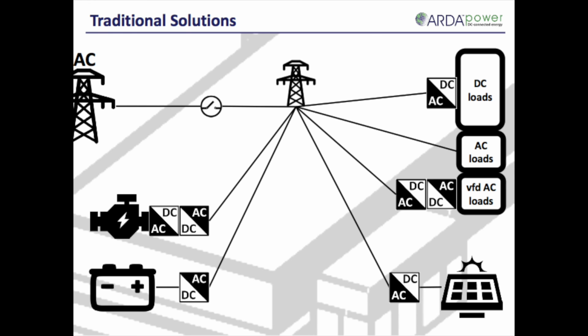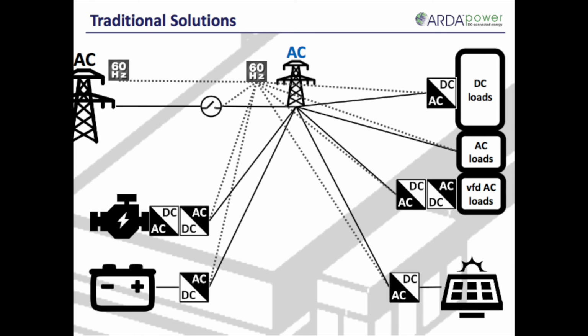For legacy reasons, and because most distribution is AC-based, traditional microgrid solutions are also AC-based. As a result, they must stabilize voltage, frequency, and phase, and be concerned with reactive power flows. And since they typically use the macrogrid to synchronize the microgrid, they need to resynchronize when the macrogrid goes down.